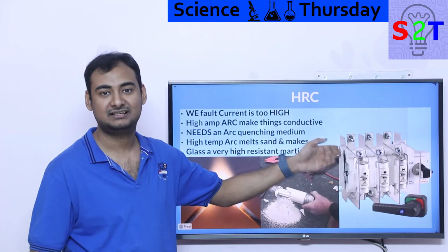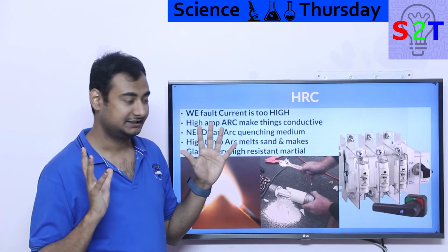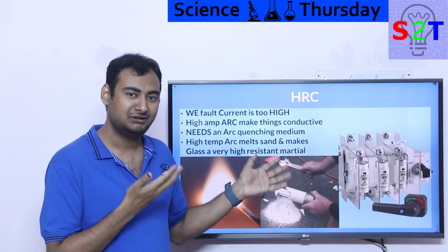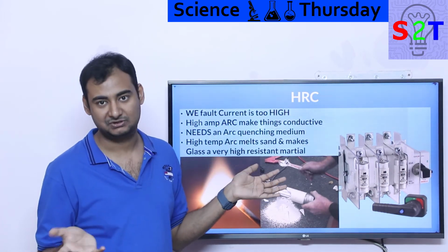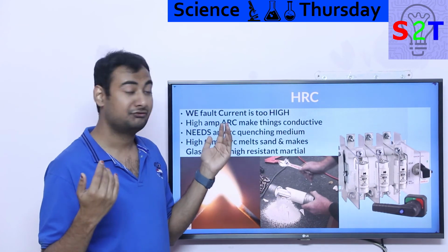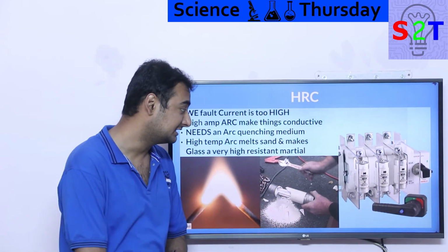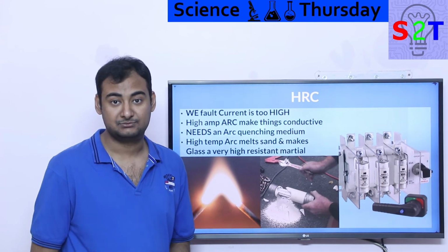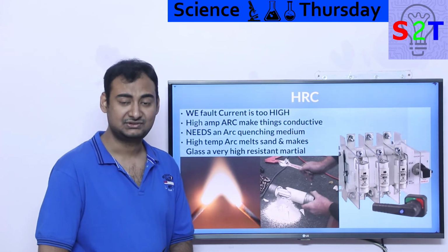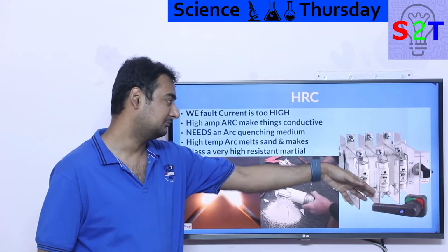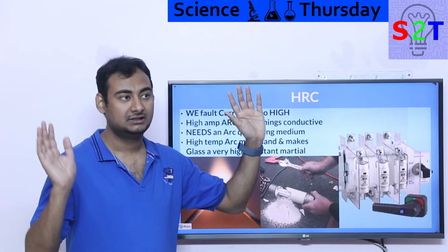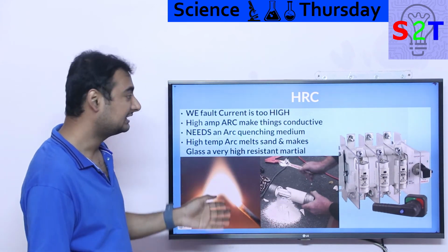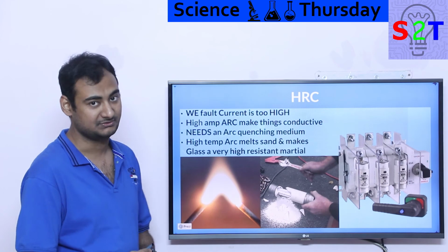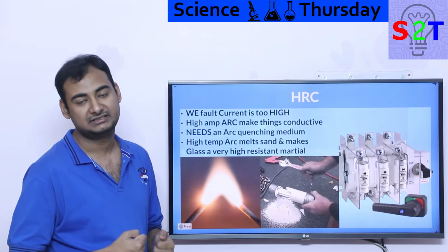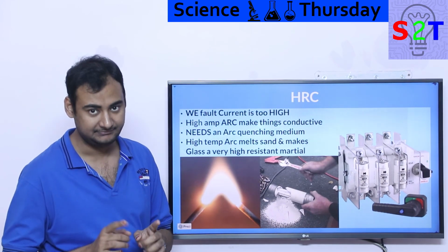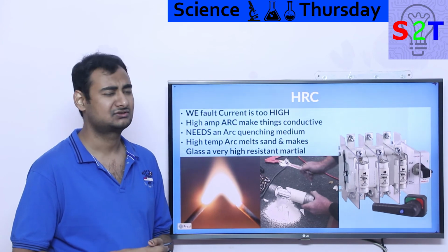The idea with these shields is, because these fuses are human-made devices, they are susceptible to quality control issues, mismanagement or faulty rating. Heck, you may put in something that is designed for, let's say, only 10,000 amps, but you're supposed to put in a 100,000 amp fuse. You could have an arc that could just jump through to another phase, and if that happens, God help you. So that is why we utilize high rupture systems when we need ludicrously high power to be handled safely. And I have provided a Siemens video down below that is quite amazing.